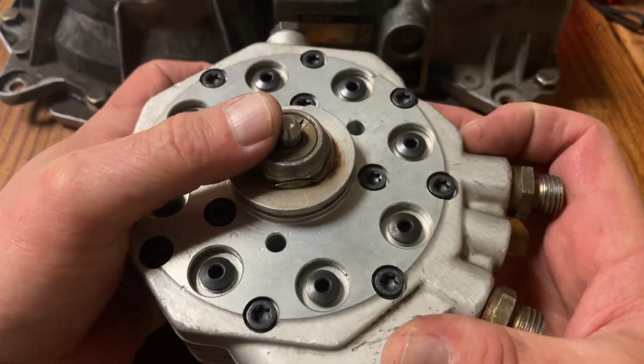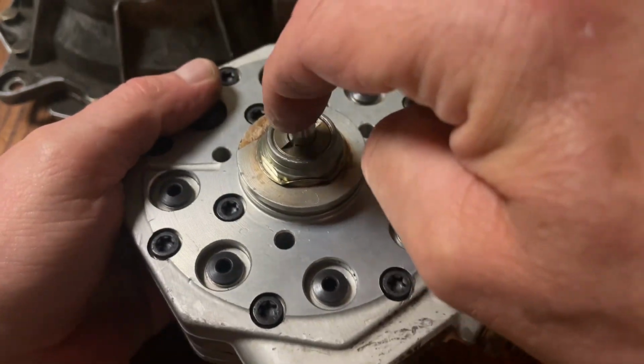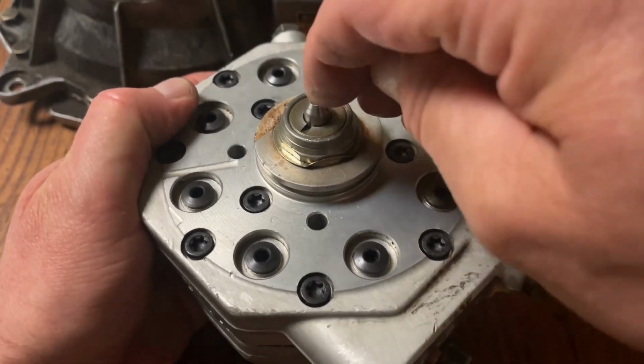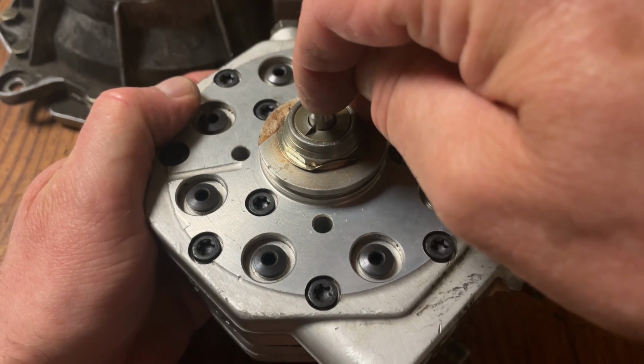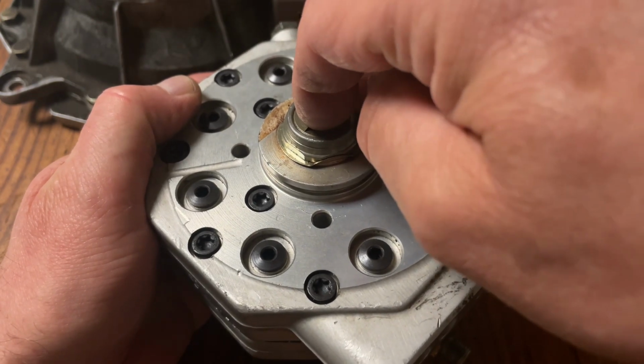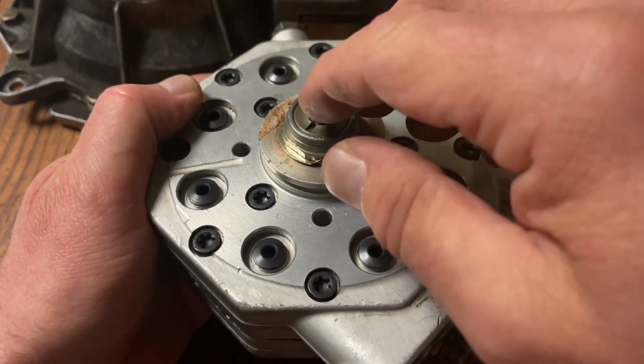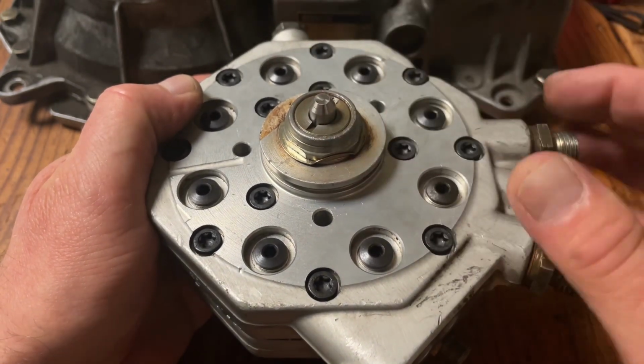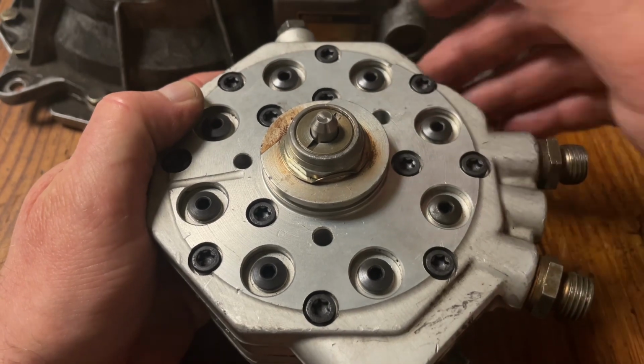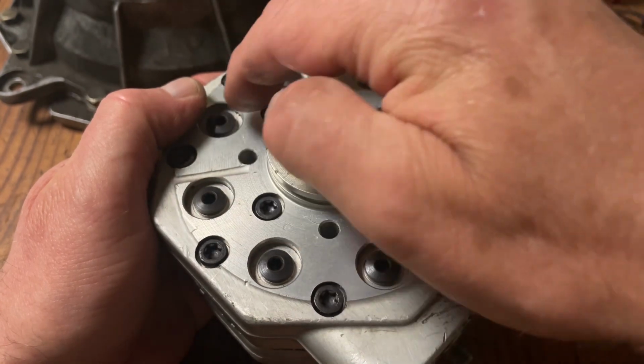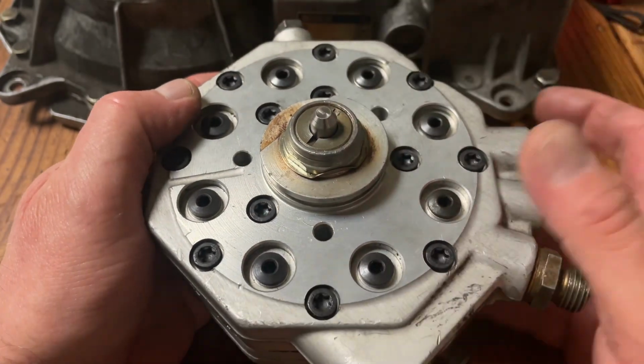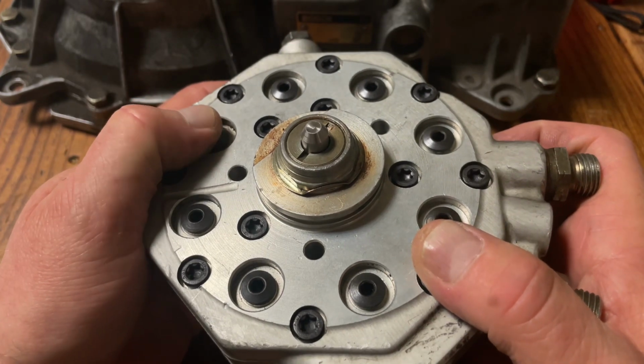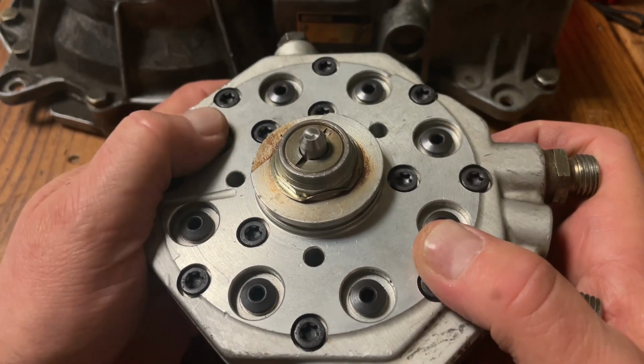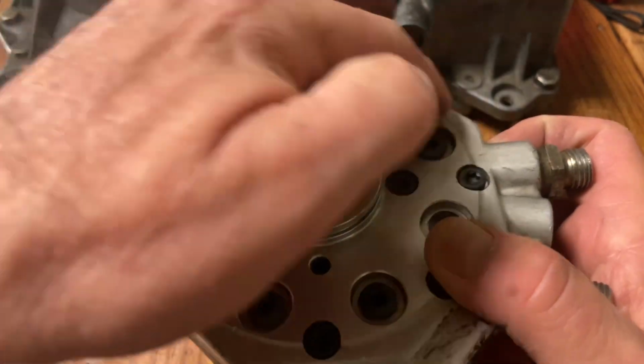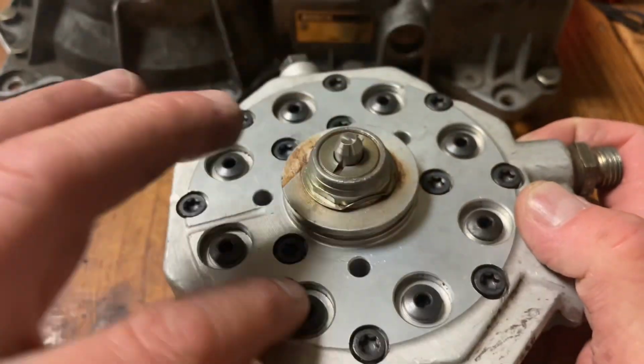And then they have a micro adjuster that is basically a rod which is coming in because this is held in a fixture. And you come down with this here, and then you set this, you measure this. This is 0, 100, and then they have a dial gauge on there where they can set this to 5%. And then you look at all 8 gauges for your flow, and you start to adjust 1 to whatever value you need in terms of liters per minute. I can't remember what that was. And then you adjust the first one, and then you bring all the other ones into synchronization.